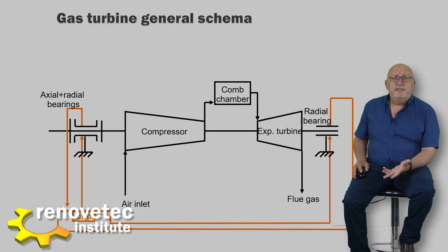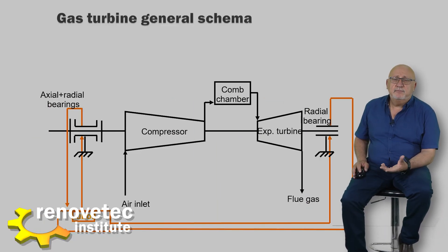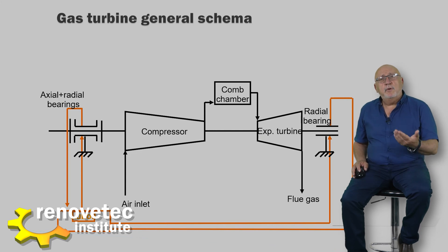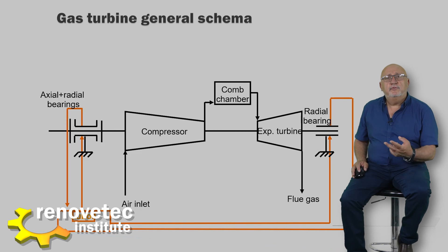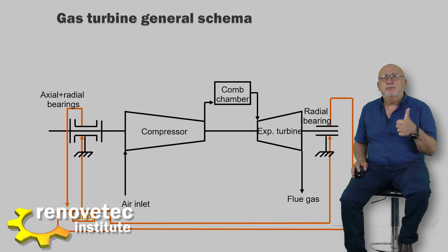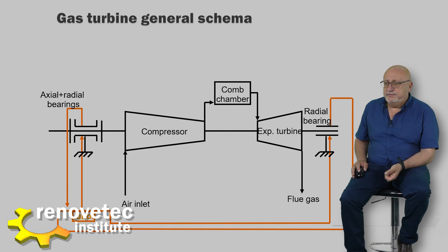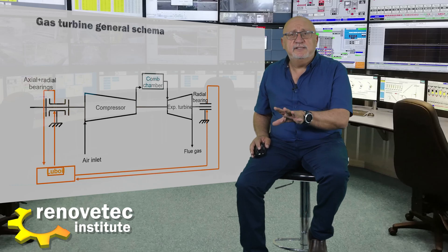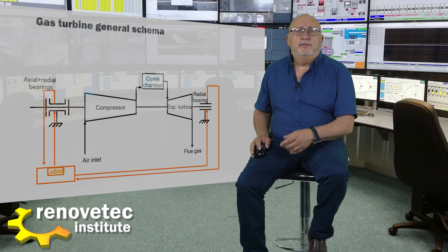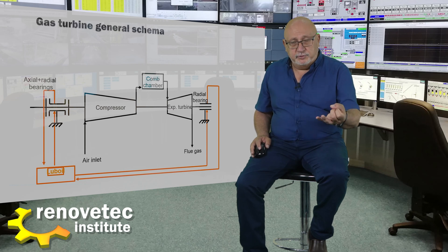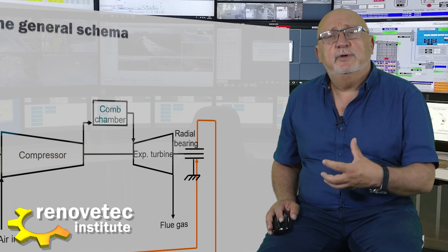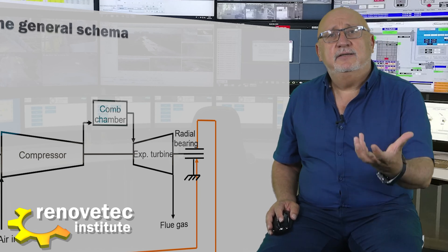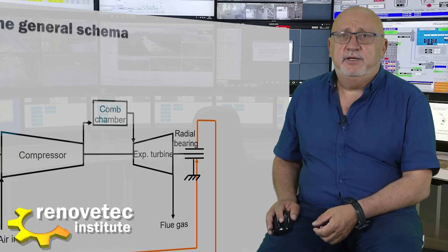In order to reduce friction, we need a system that supplies oil for two functions: first, to lubricate, and second, to cool. We therefore have a lube oil system with pumps, a reservoir, filters, and a system to evacuate the heat captured in the bearings.